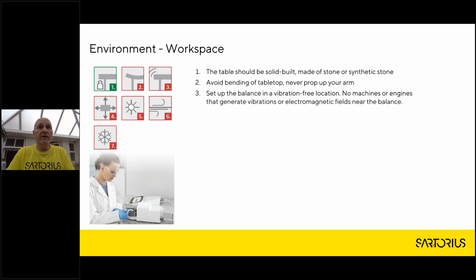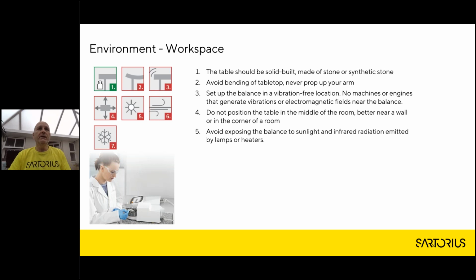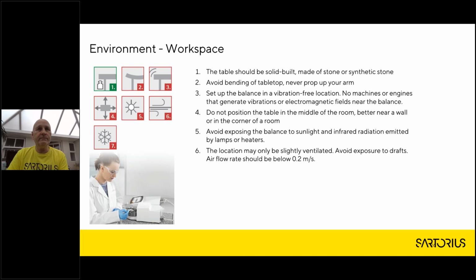Set up your balance in a vibration-free location. No machines or other equipment which will generate vibrations or electromagnetic fields near to the balance. Always position your balance table, if you can, in the corner of a room or at the edge of a room near a wall where you will have more support and less vibrations. Avoid exposing it, as we talked about previously, to direct sunlight and any infrared radiation emitted by lamps or heaters.